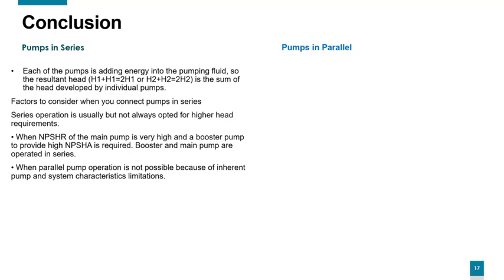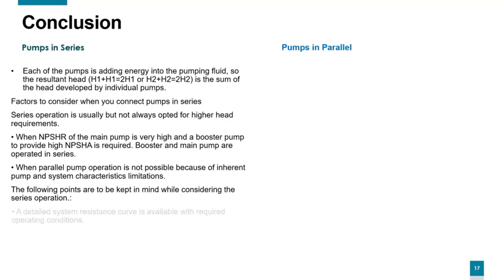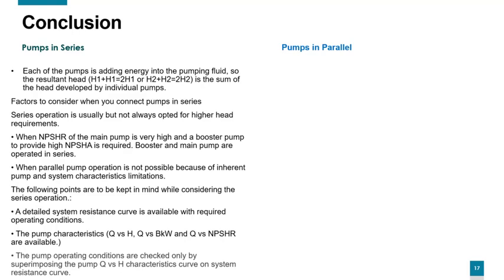When parallel pump operation is not possible because of inherent pump and system characteristics limitations. The following points are to be kept in mind while considering the series operation. First, a detailed system resistance curve is available with required operation condition. Second, the pump characteristics are available, QH, etc. And finally, the pump operating conditions are checked by only superimposing the pump Q versus H characteristics curve on system resistance curve.